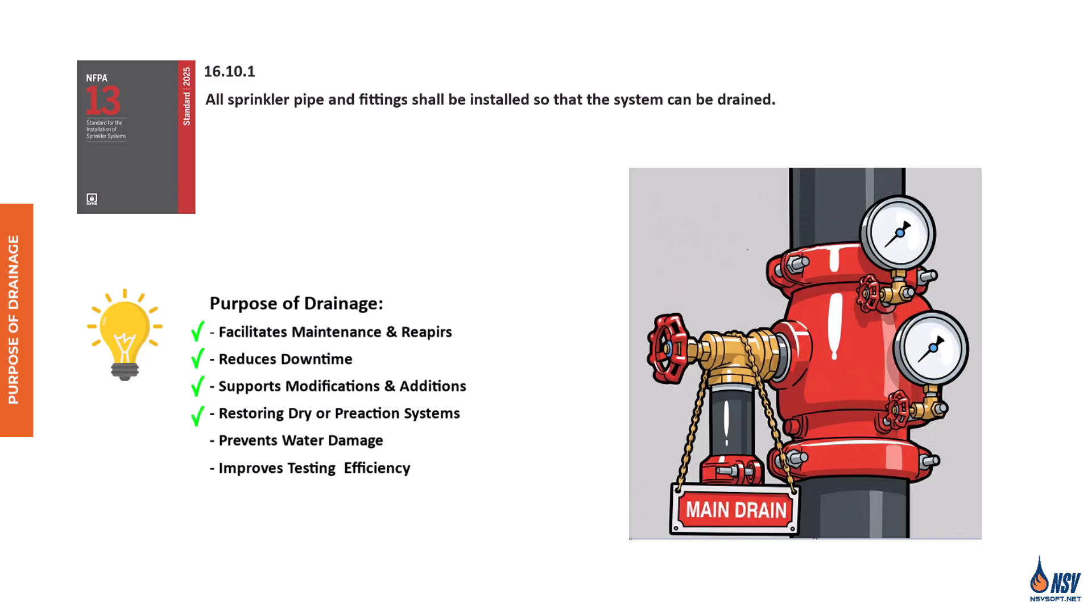Restoring dry or pre-action systems: dry and pre-action systems must be fully drained before resetting. Drainage ensures that trapped water is removed, preventing corrosion, freezing, or false alarms. Prevents water damage: controlled drainage avoids accidental discharge inside the building, protecting property and equipment. Improves testing efficiency: drainage is essential for accurate flow tests like the main drain test. It ensures accurate results and helps identify obstructions or pressure drops in the system.